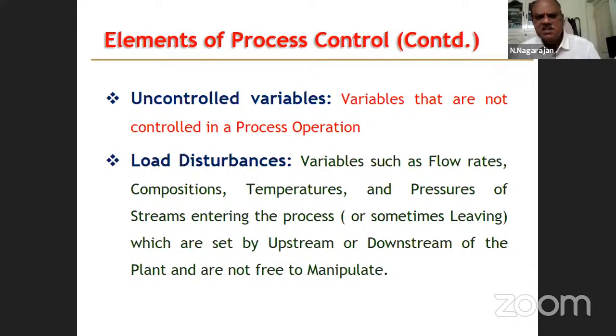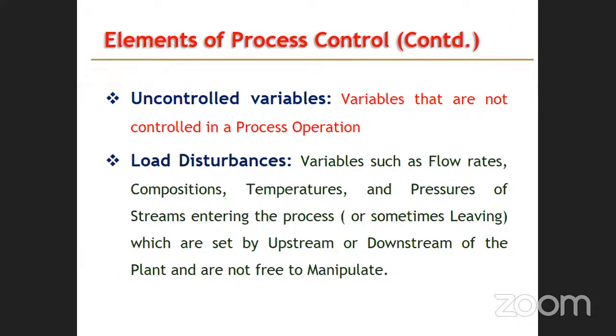And load disturbances are variables such as flow rates, composition, temperatures, and pressures of streams entering the process or leaving the process, which are set by the upstream or downstream of the plant. Because any equipment receives something from its upstream and then it sends its output to the downstream. So there can be load disturbances, the inputs can vary, or the requirement of the output going to the next process. If the next process is reducing its capacity, that will affect your upstream equipment. So these are called load disturbances.